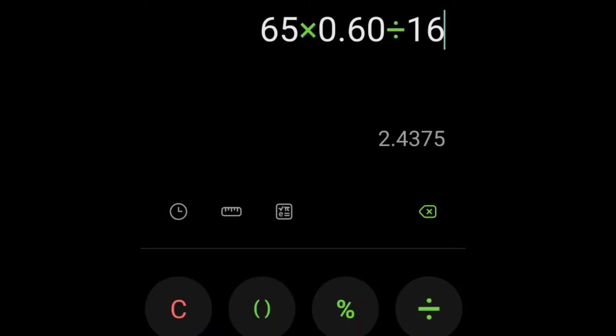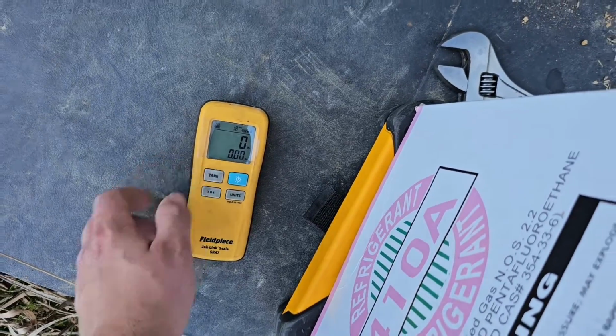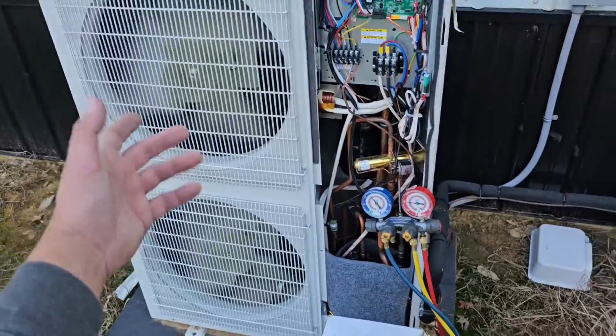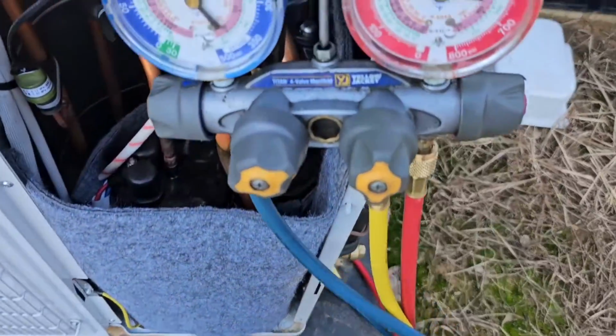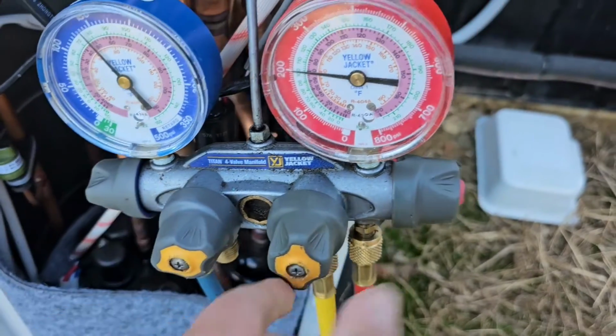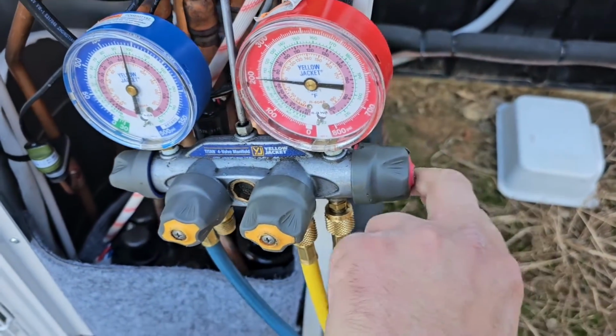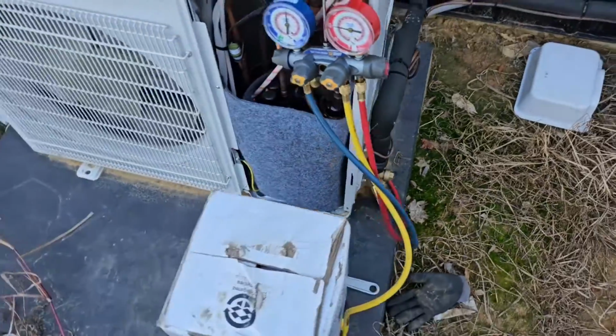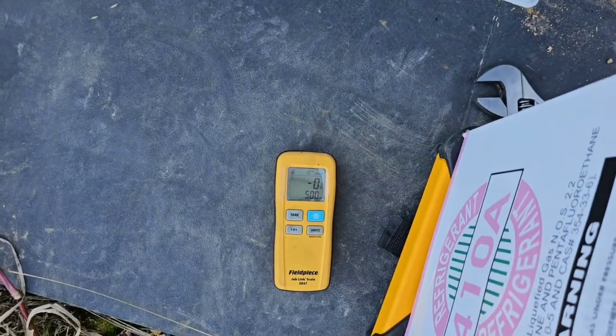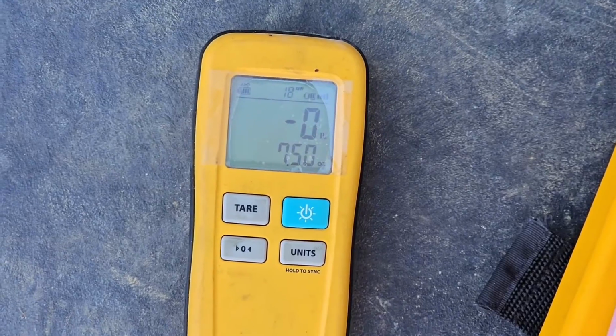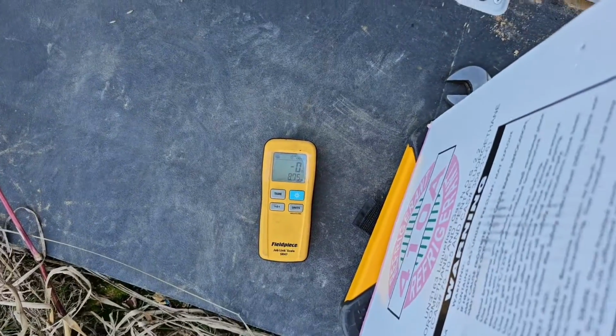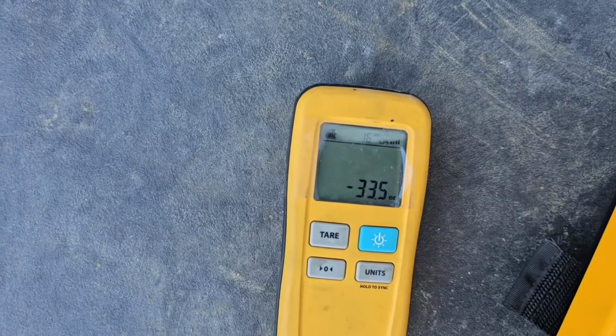All right, so using the calculator, we're just going to go 65 times 0.60. Look at that, 39 ounces divided by 16. That's almost, well, that's 2.5 pounds. So 2.4. Zero out the scales. Unit's running, and now we're going to add. Make sure this is closed. All right. Almost there.